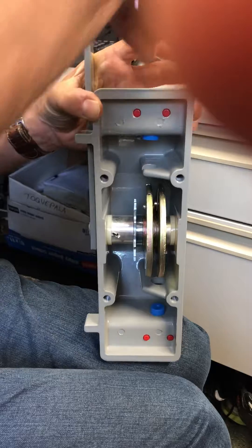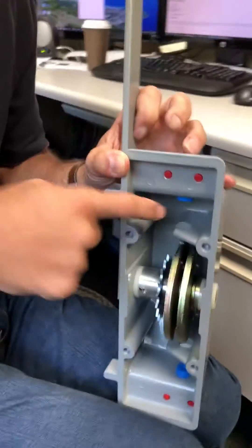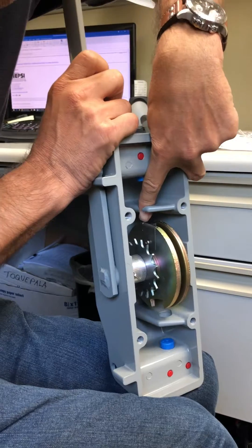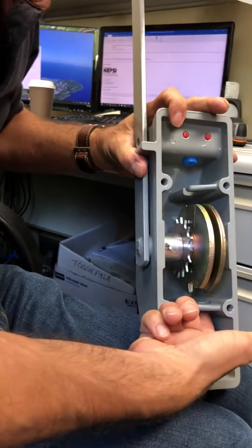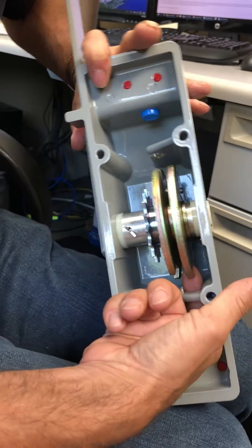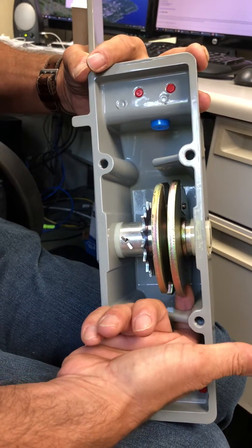There's a lock placed in the disconnect handle up here on top — a Kirk Key interlock up here on top. The lock cylinder extends through this hole and is covered. You can see the lock cannot be extended in this position, but down here the lock gets extended and goes into the inside disc. The lock cylinder extends and the key can be released.